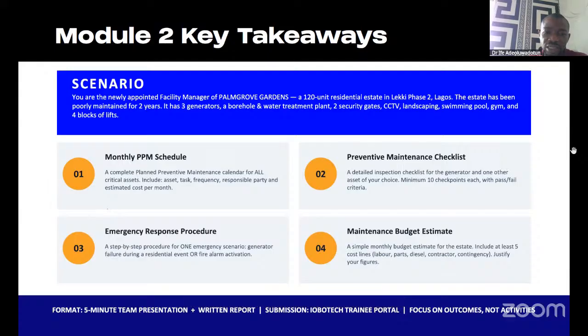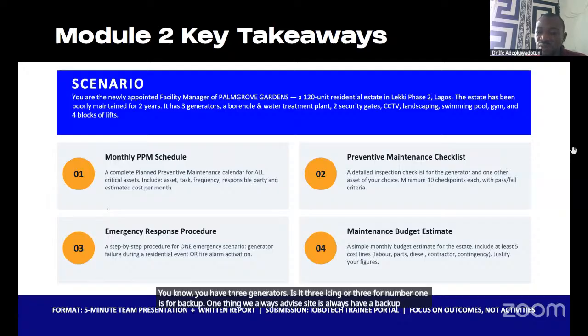Emergency preparedness for generator failure: first, find out if you have a backup. If you have three generators, are all three in use, or is one kept as backup? We always advise sites to have a backup generator, not just one. If you only have one, make sure you have the contact of a rental company that can supply one within an hour or two.